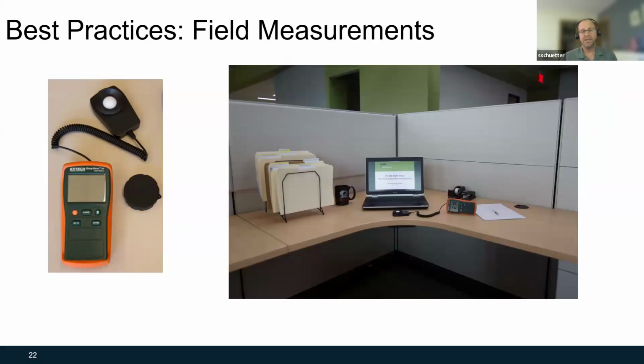If field measurement is needed to confirm target illuminance values have been achieved or to investigate existing light levels prior to a retrofit, there are some best practices to keep in mind. The light meter should be placed on the work plane or held away from your body so that you do not cast a shadow on the sensor. It's best to record measurements at a location where tasks will be performed and not in the corners of a space or directly below a light fixture.